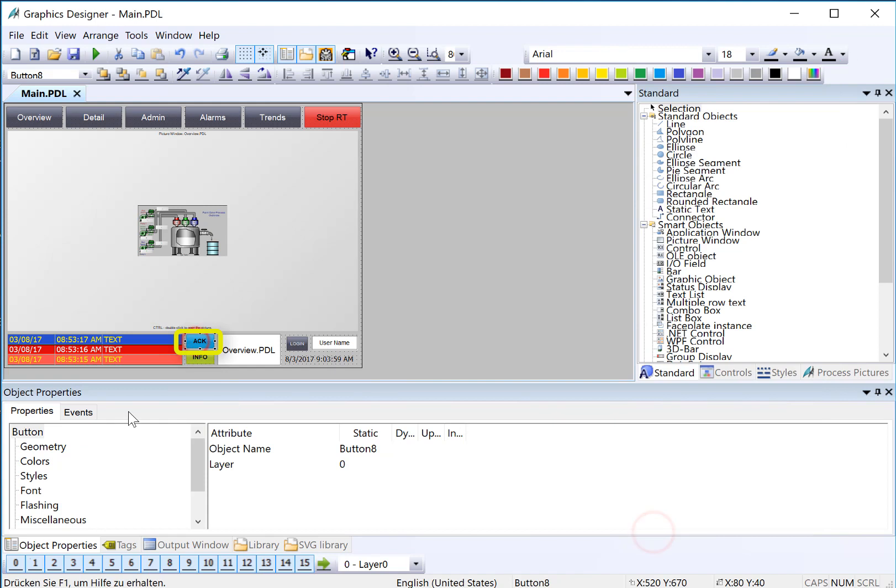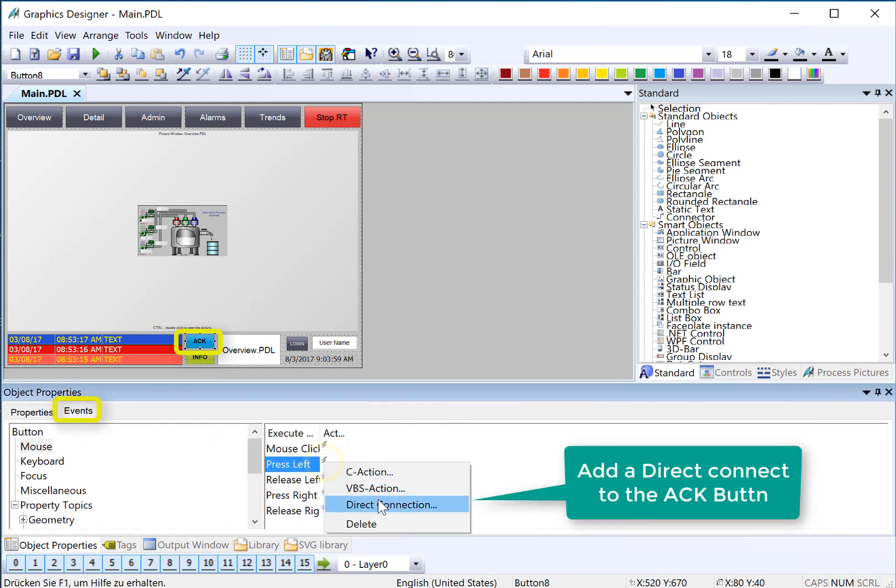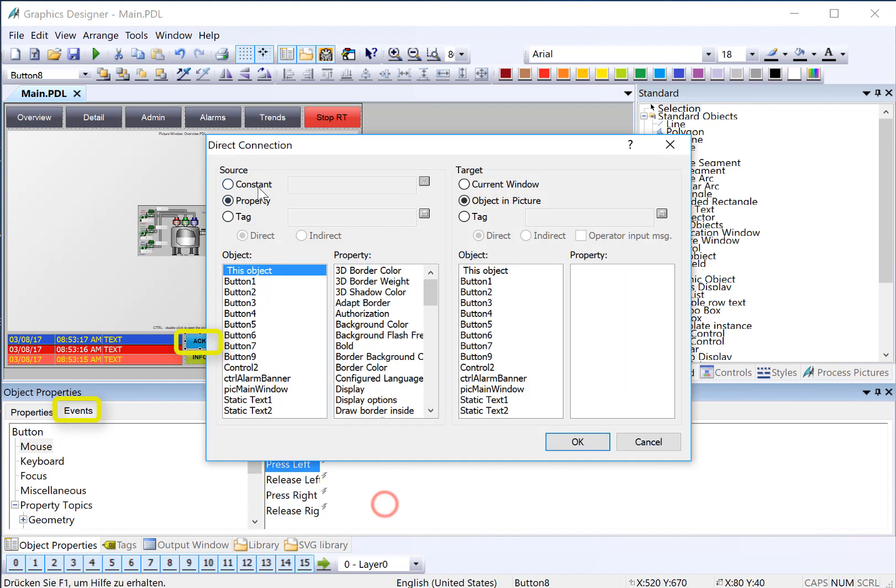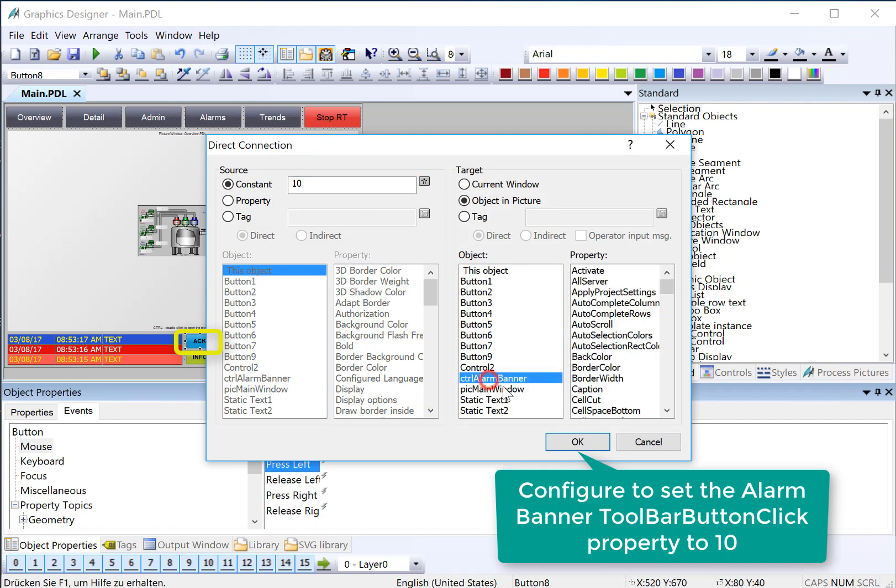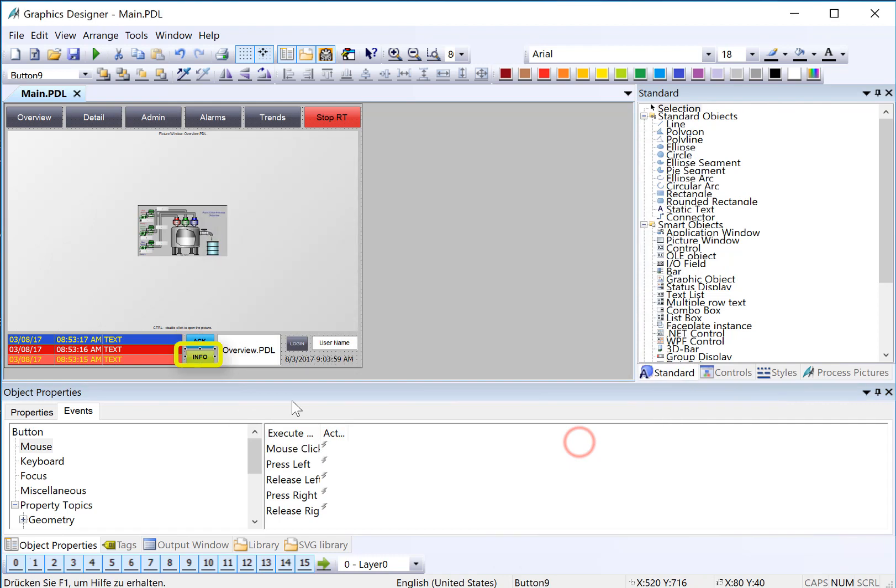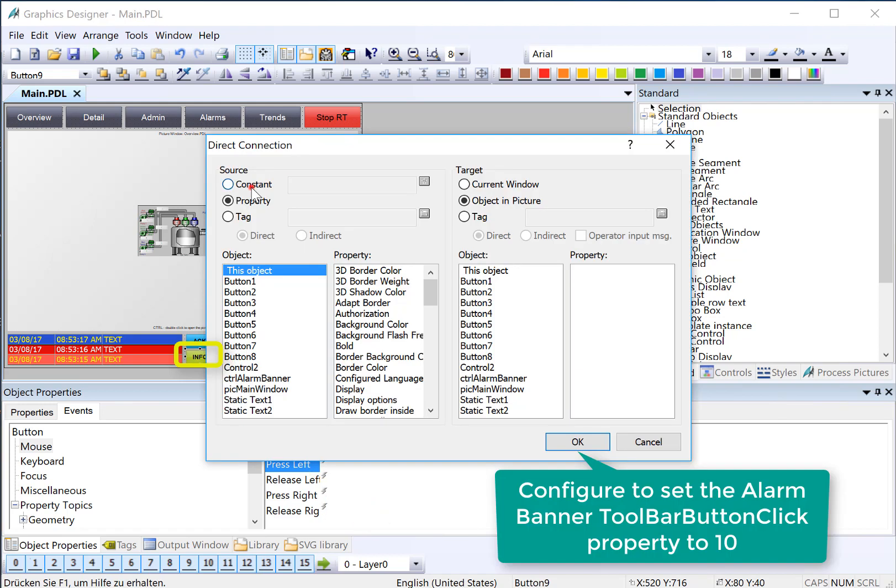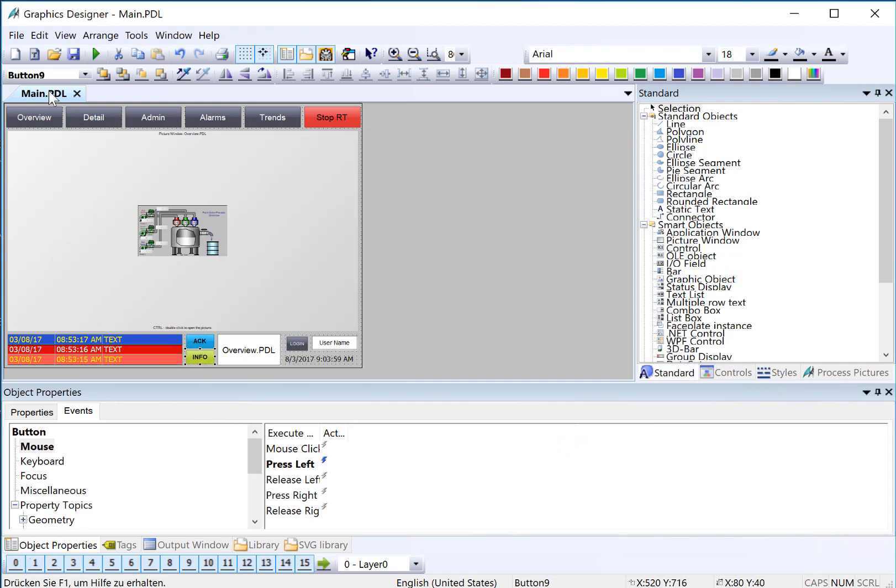We'll do the Ack button first. We'll go to Events and choose Direct Connect on our press left. We'll put the object ID in the constant, and since we've named this well, it's easy to pick out our alarm banner. There is a property called ToolbarButtonClick. If we send a number into that property, it's like pressing the corresponding button on the toolbar. If we send it a 10, it's going to acknowledge whatever alarm is selected on the control. We'll do the same thing on our Info button. There's our toolbar button click, and just click OK. Then we'll save.